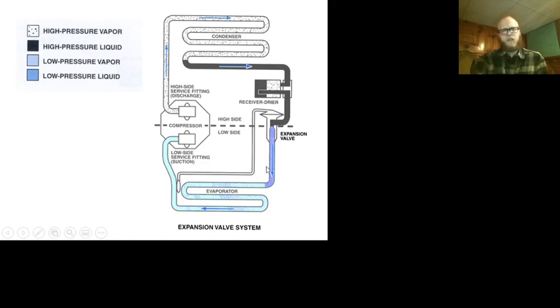In this system with an expansion valve, we have a receiver dryer, and that's between the outlet of the condenser and the inlet to our expansion valve. This receiver dryer would normally sit upright, not on its side like that. And you see how the straw for my input to the expansion valve is in the bottom? The whole point of that receiver dryer is to make sure that liquid refrigerant gets to the valve.